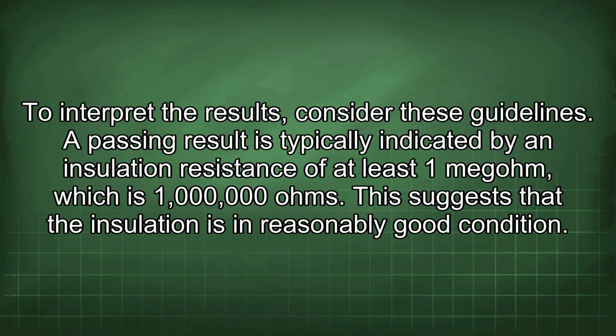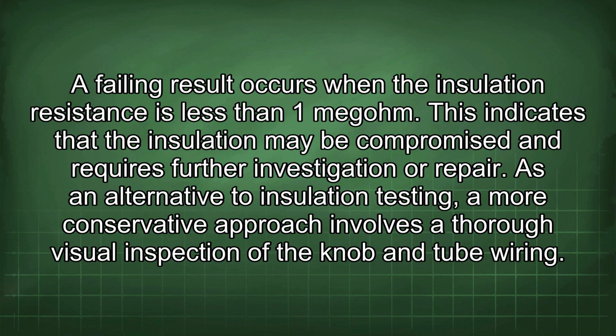To interpret the results, consider these guidelines. A passing result is typically indicated by an insulation resistance of at least 1 megaohm, which is 1 million ohms. This suggests that the insulation is in reasonably good condition. A failing result occurs when the insulation resistance is less than 1 megaohm. This indicates that the insulation may be compromised and requires further investigation or repair.